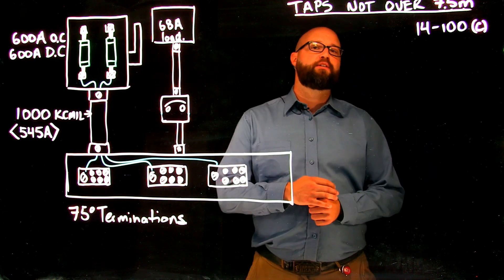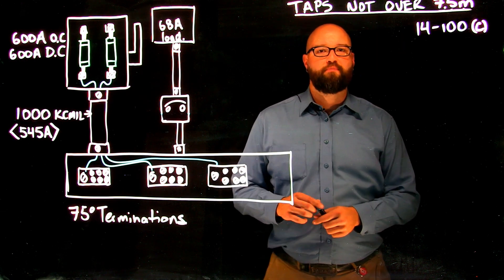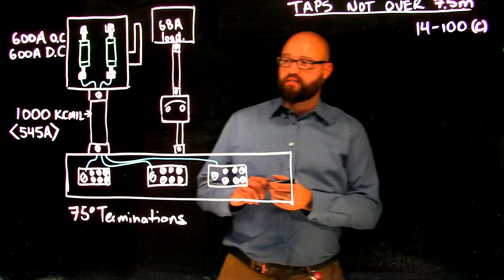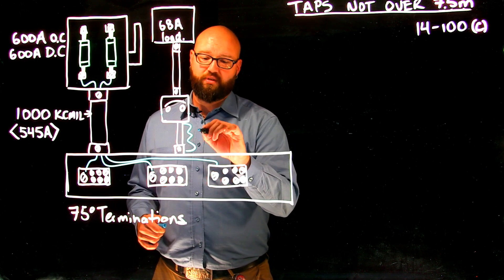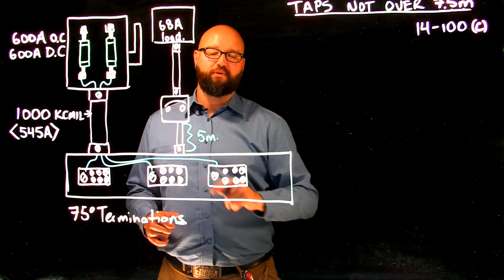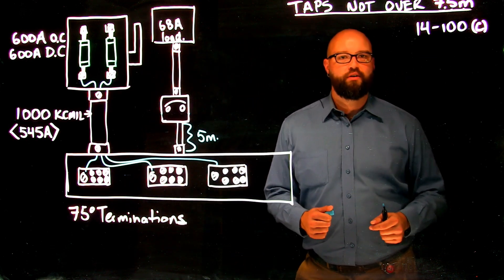In this video we are looking at tap conductors that are over three meters but not over 7.5 meters. So we're gonna take a look. Here's our tap conductor. This is we're gonna say five meters. That puts us above the three meter mark but under the 7.5 as required by 14-100(c).